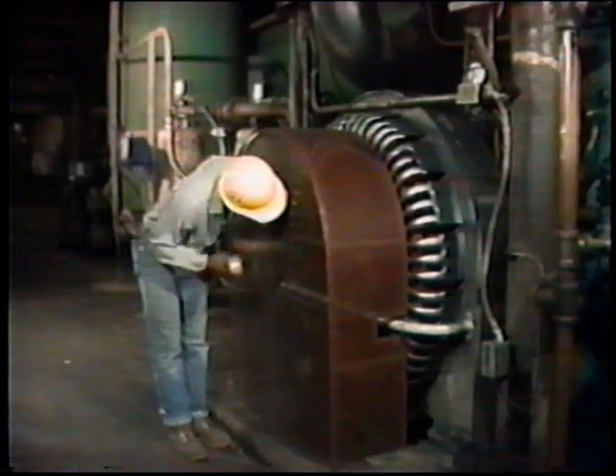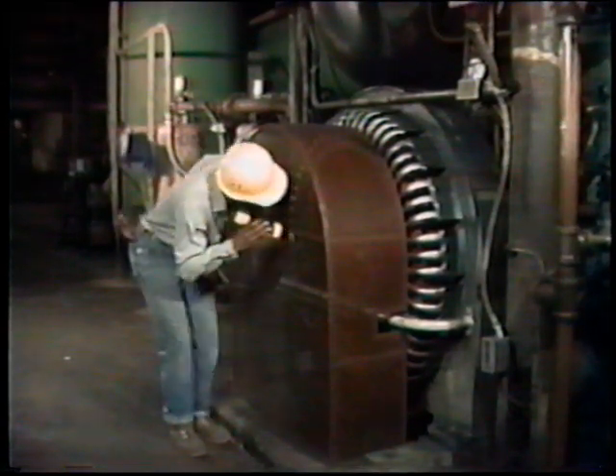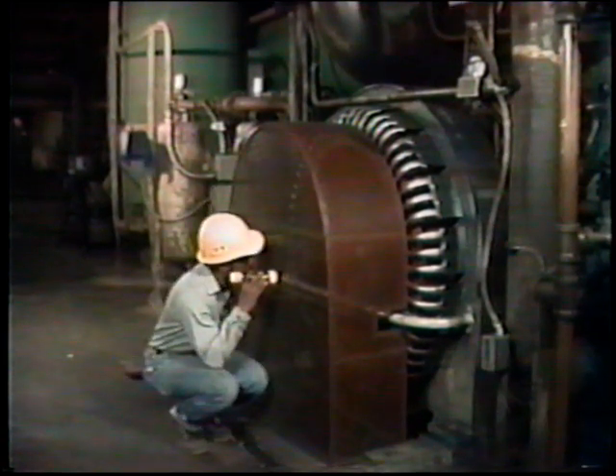By using a flashlight and looking through the motor's protective screen, you may be able to see the stator windings. Examine the windings carefully. Look for discoloration, signs of burnt insulation, and dirt. After checking the stator windings, visually examine the motor's brushes, brush rigging, and slip rings. Take notice of the surface of the slip rings and check for grooving or discoloration. Also look for wearing of the brushes and sparking.